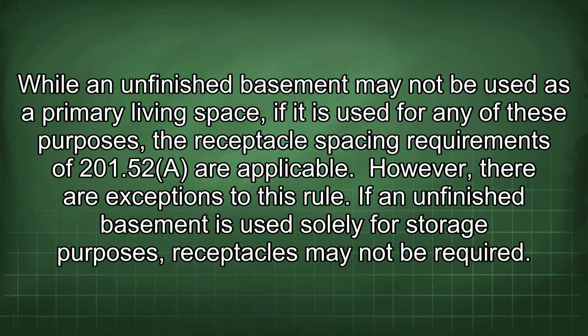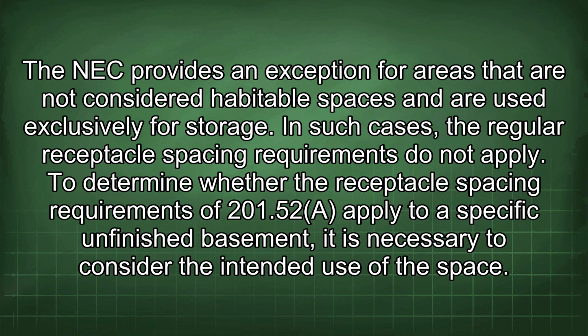However, there are exceptions to this rule. If an unfinished basement is used solely for storage purposes, receptacles may not be required. The NEC provides an exception for areas that are not considered habitable spaces and are used exclusively for storage. In such cases, the regular receptacle spacing requirements do not apply.